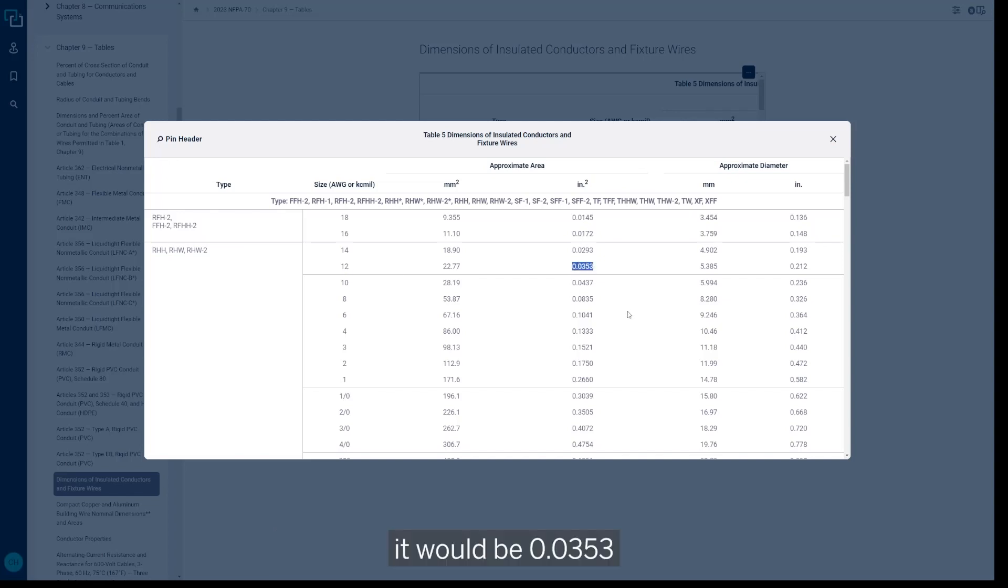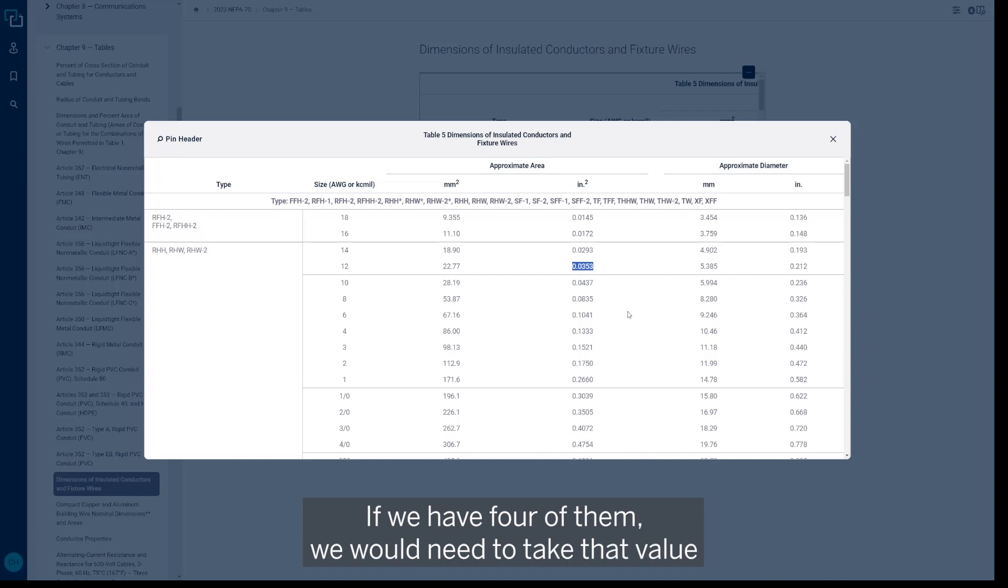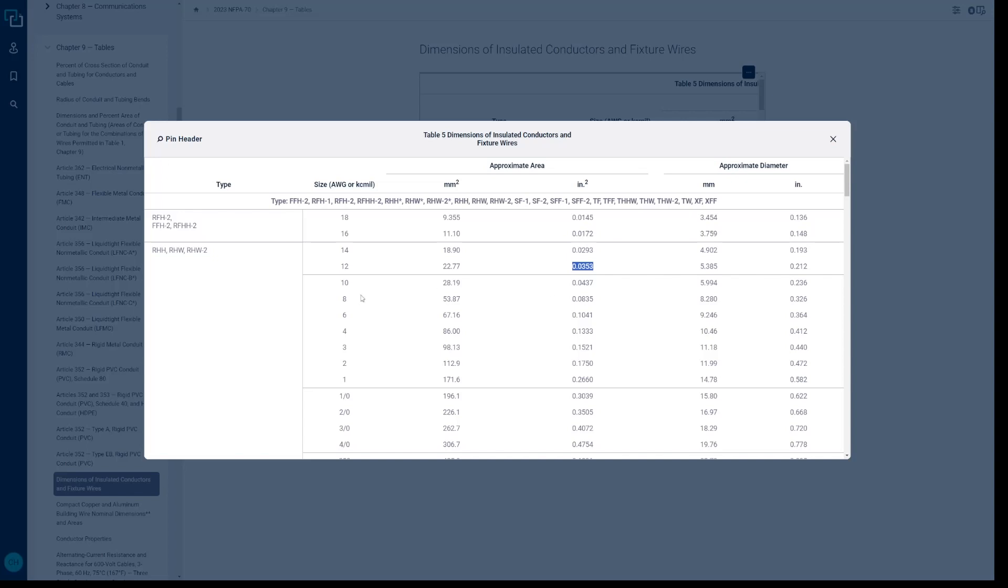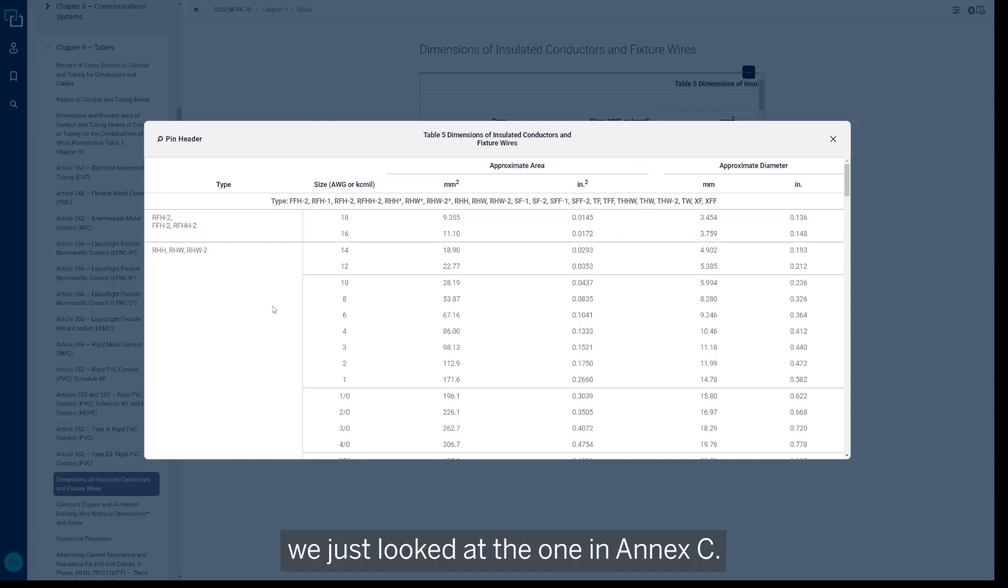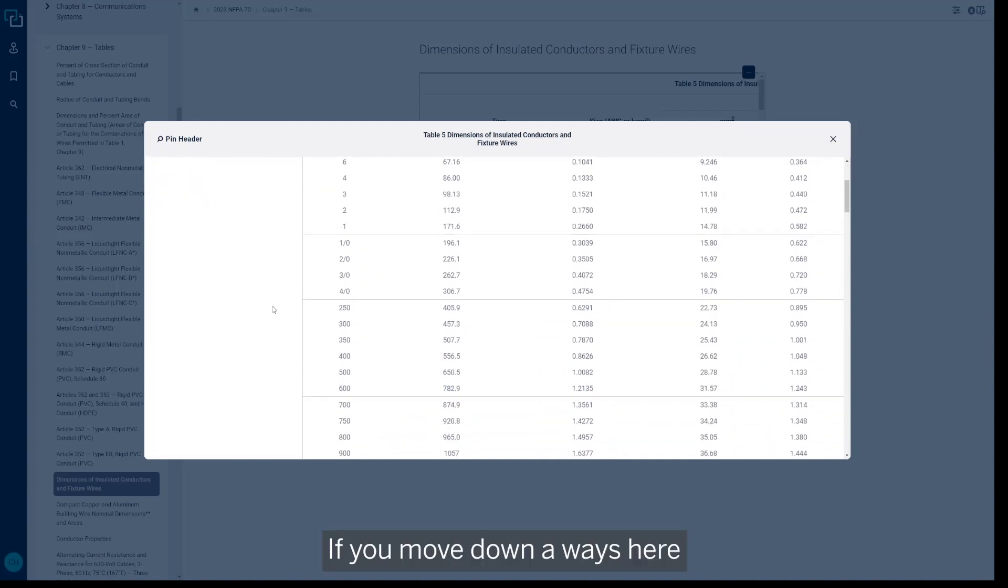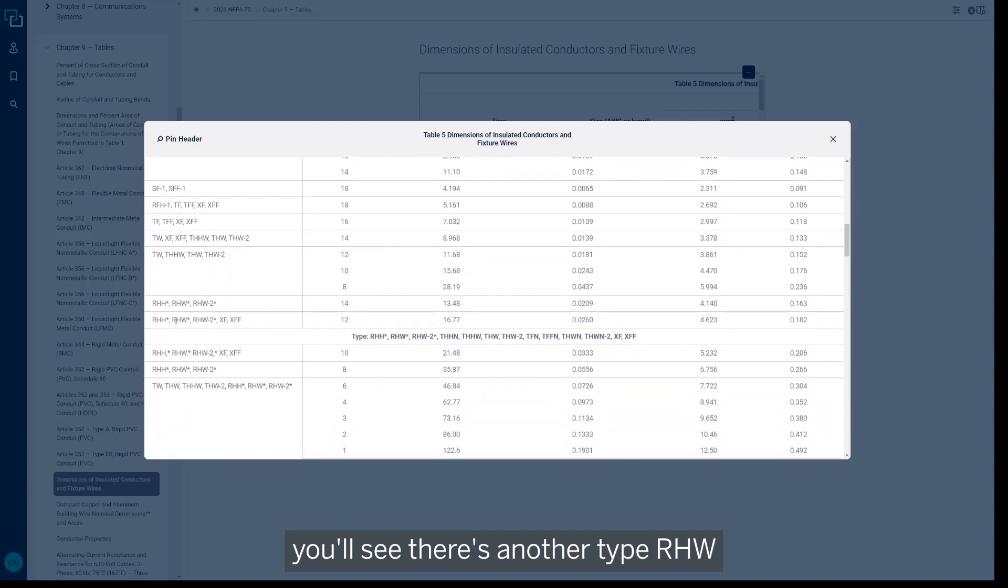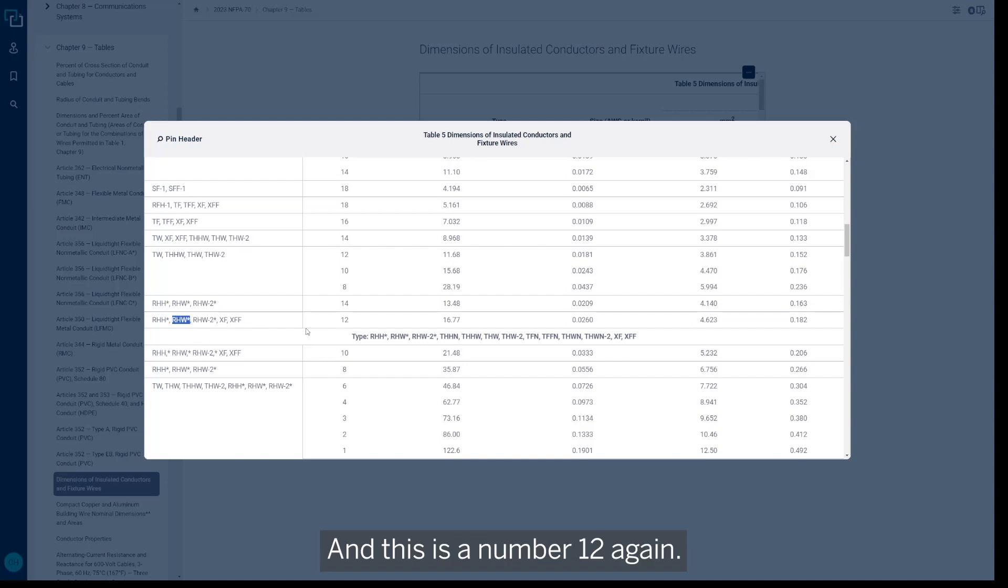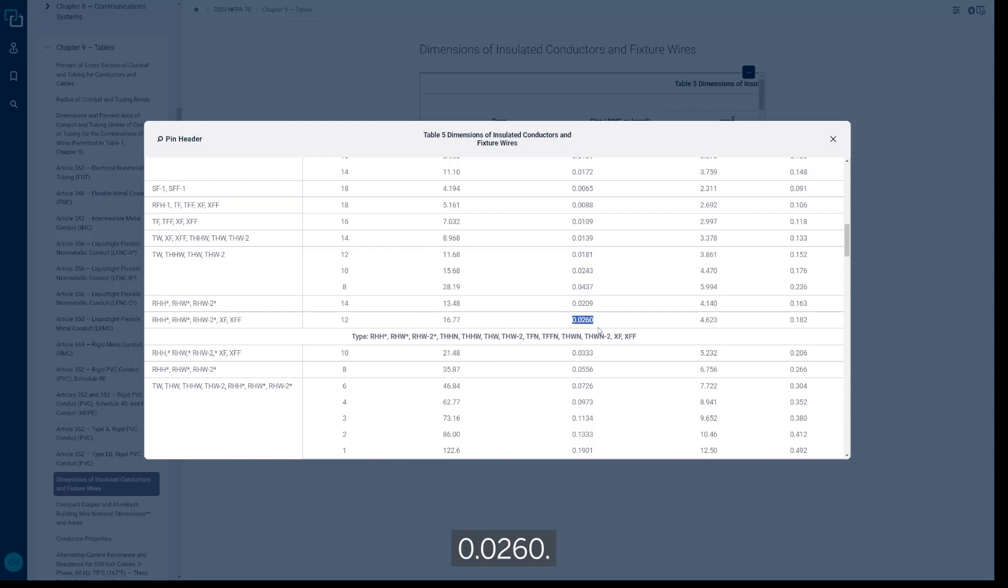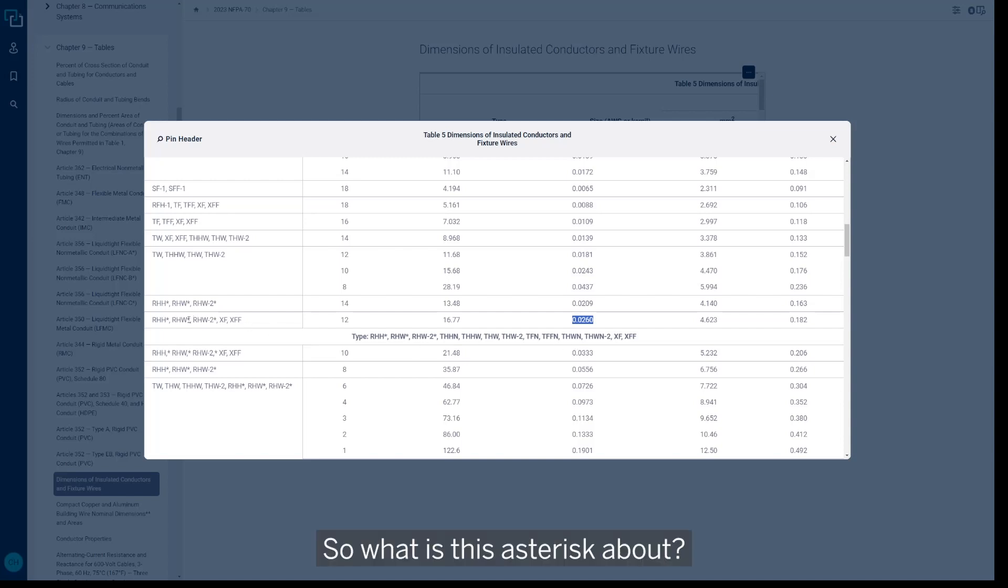So if we're going to have a type RHW like we've been talking about, number 12, it would be 0.0353—that's the value we would use for one number 12 RHW. If we have four of them, we would need to take that value four times, add it together and come up with a total. Something to be conscientious about in Table 5, or any table for that matter where there's an asterisk—we just looked at the one in Annex C. If you move down a ways here, you'll see there's another type RHW that has an asterisk next to it at the end. Okay, and this is number 12 again, so we've got the same size wire, but it gives us a different value—0.0260—so it's a little bit smaller than it was in the one that we looked at above. So what is this asterisk about?